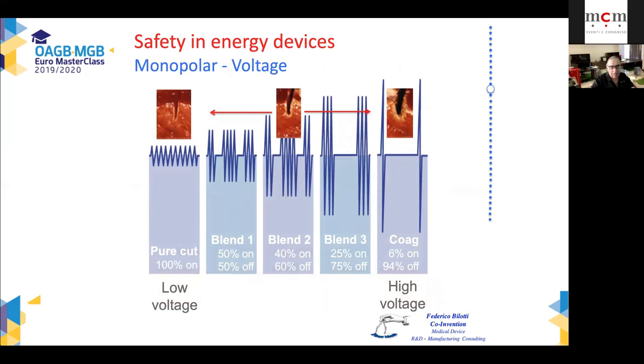The monopolar staplers, devices, I'm too used to talking about staplers. The monopolar devices can be used at low voltage or high voltage. What is the difference? Well, look at that cut on the tissue. That cut on the tissue can be nice and clean like a scalpel, or can be wide and damaging as the one to the right for high voltage. What is the difference? It is time. In low voltage, the time between discharges of electricity is very short. On the right of the image, where you have high voltage, the time between discharges of electricity is relatively larger. And that's why you allow the tissue to relax and then you zap it with electricity. And that damages tissue more.